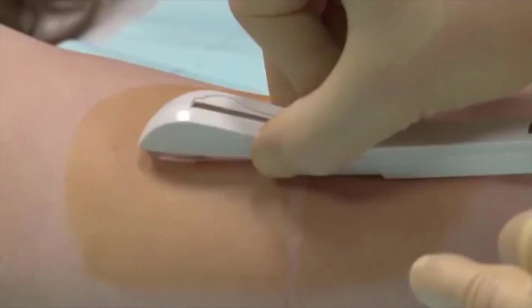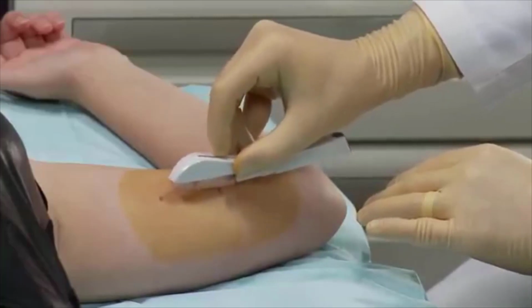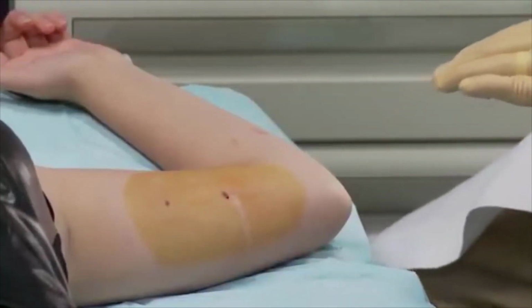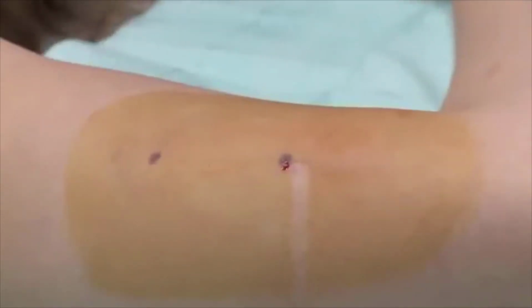The implant is now in its final subdermal position, and the needle is locked inside the body of the applicator. The applicator can now be removed. If the applicator is not kept in the same position during this procedure, or if the purple slider is not completely moved to the back, the implant will not be inserted properly.